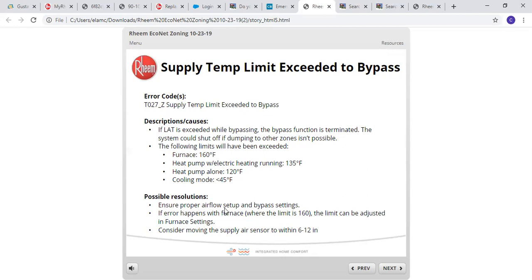Possible resolutions: ensure proper airflow setup and bypass settings. If error happens with furnace, the limit is 160, but the limit can be adjusted in the furnace settings. Consider moving the supply air sensor to within 6 to 12 inches, moving it between 6 and 12 inches.